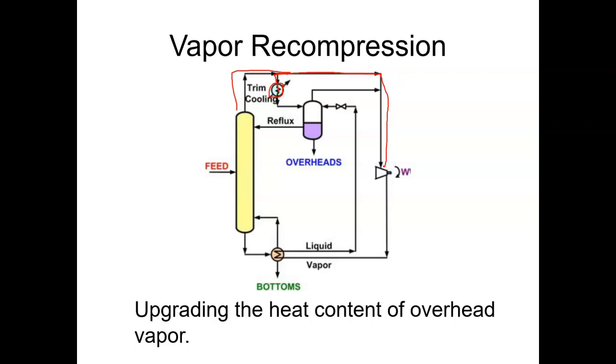This compressor will naturally compress the vapor and increase the temperature further. This vapor will then come to the reboiler. Since it has been already compressed the temperature has been increased and then it exchanges the energy with the liquid coming from the bottom of the column.